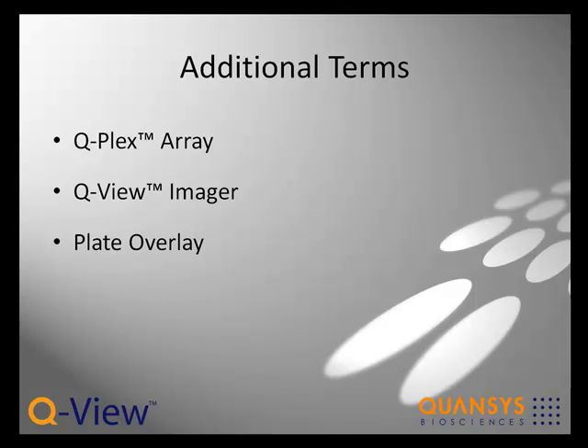It is the only imager specifically designed to be used as a system with QView software and QPlex arrays. Plate overlay refers to the diagram of the plate that is aligned by the user over the plate image. Product code is the alphanumeric code that defines parameters such as the number of spots per well and their positions, and the concentrations of each analyte in the calibrator, and the optimal curve fit settings.